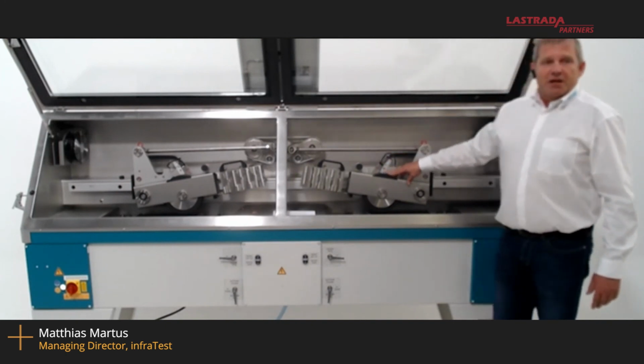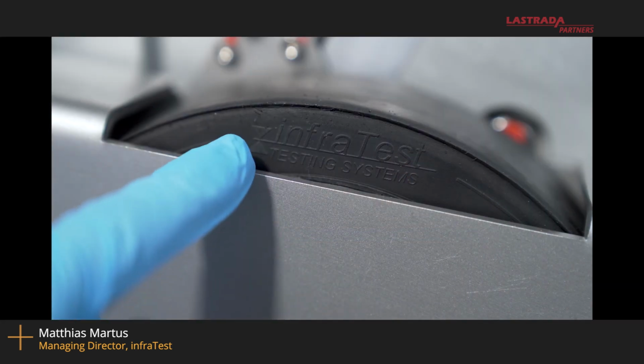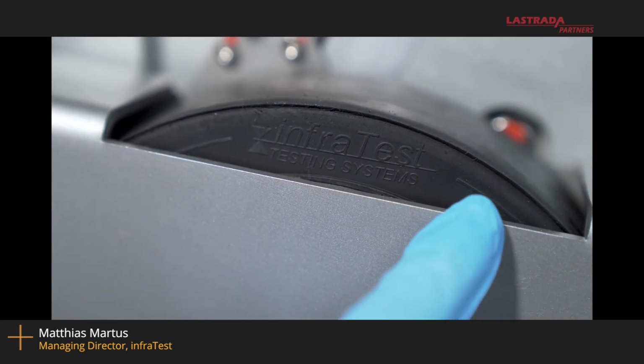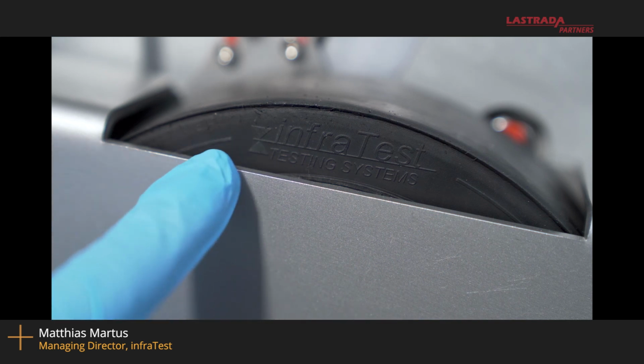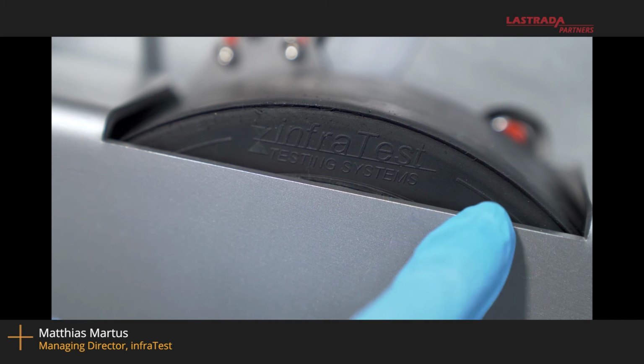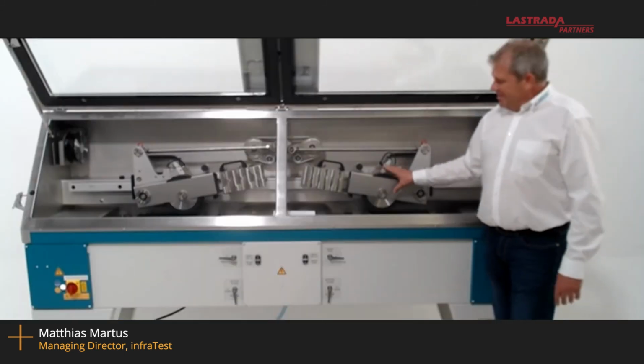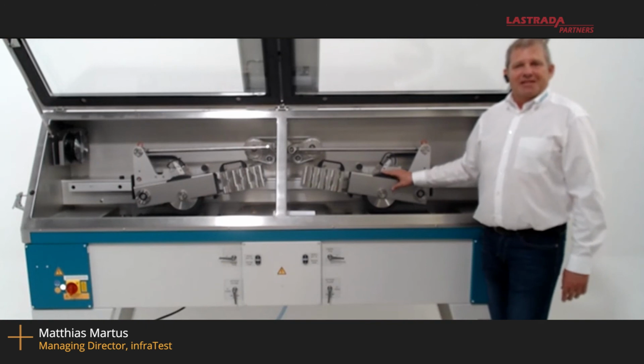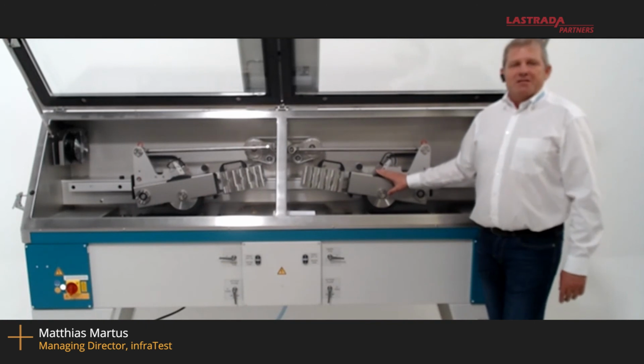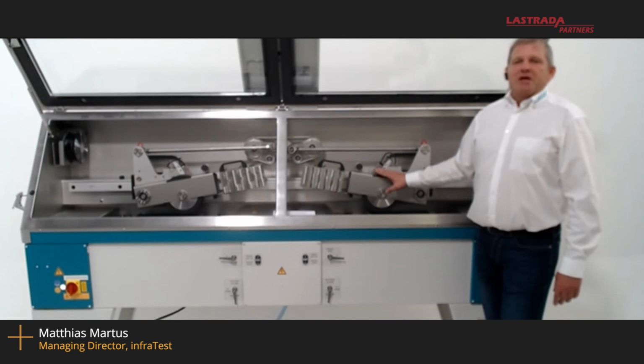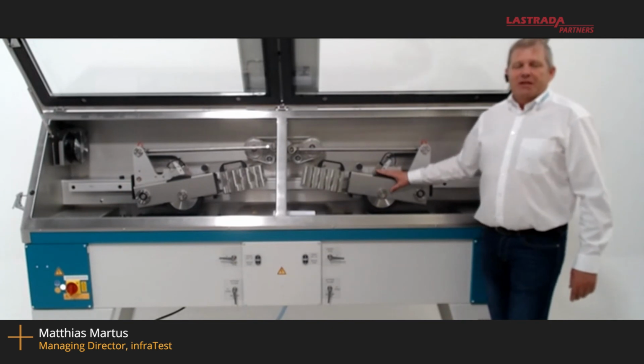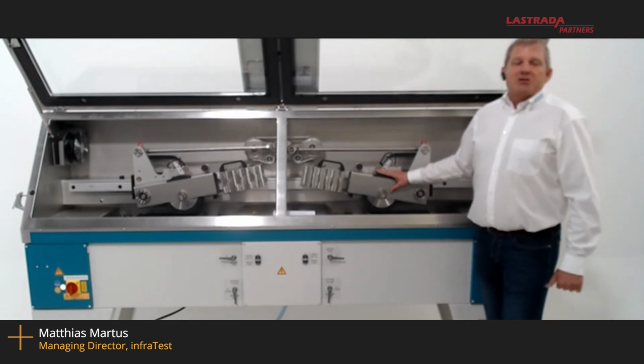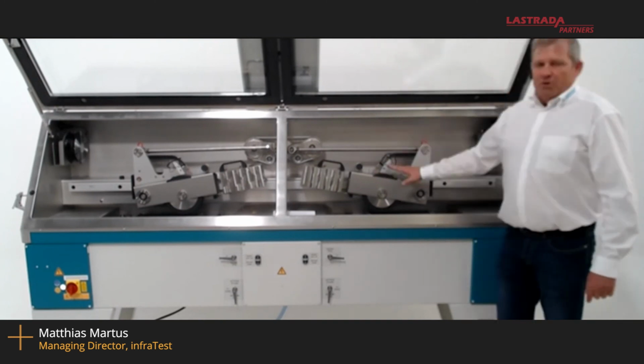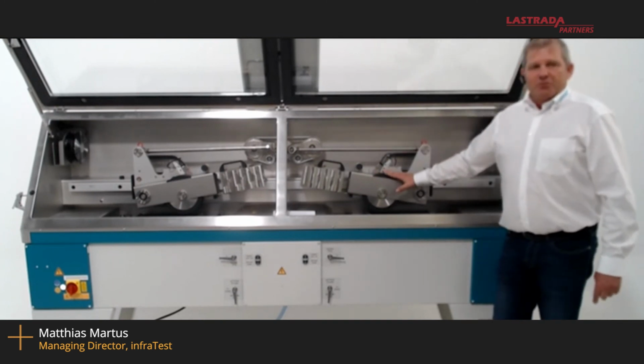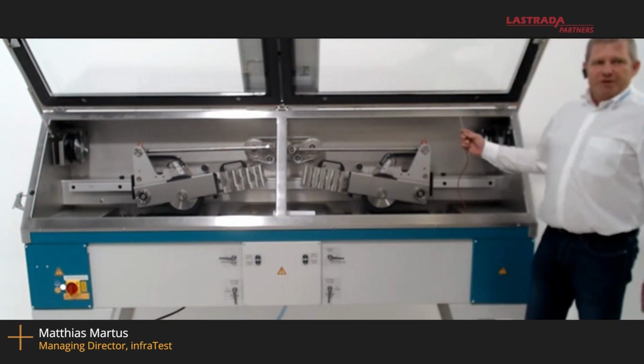The other thing is, especially if you use rubber wheels, you have some friction on the rubber wheel. You have some wear on the rubber wheels, so that after a certain time, the rubber wheel gets unround. We make this interview just before Easter, so you get more or less a big Easter egg on the machine, and you have to test this roundness. I also would say once a year, because the unroundness, if you have an Easter egg here on the machine, goes directly into the measuring results. So displacement, roundness of the wheel, and of course function of the PT100.